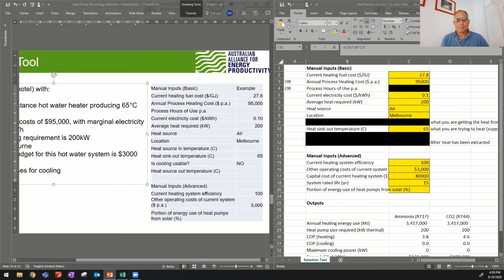Just to clarify on that point, your refrigerator at home has butane in it currently, so that's a natural refrigerant we're not including. The limiting factor with isobutane, butane, and propane as refrigerants is they go bang very happily, so you're limited by the size of the charge in the unit. They're currently working on adding CO2 to these refrigerants and working out a safer way to use them. But if you turned up to a large industrial site and said you'll put a butane or propane heat pump in here with 200 kilograms of charge - all good, but you'll probably level the building if it leaks.